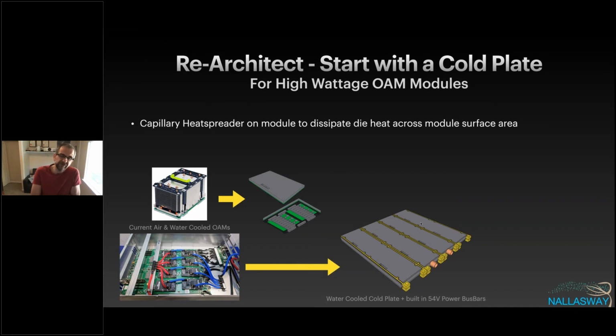And because we have such huge power problems, we need to bring a kilowatt per module - that's 8 kilowatts, even at 54 volts, a huge amount of power. We're concerned about the heating of the UBB motherboard to actually bring the power in through many 2-ounce copper planes and a very expensive PCB. So we could actually route the copper bus bars into the cold plate.